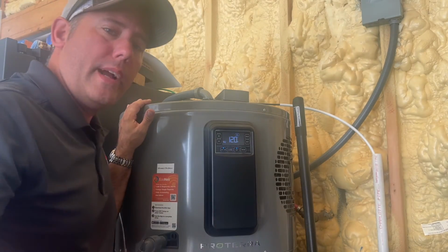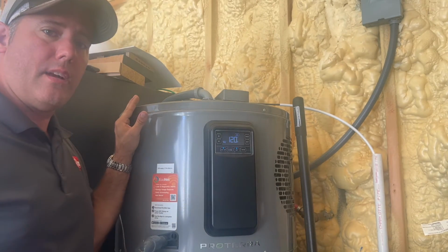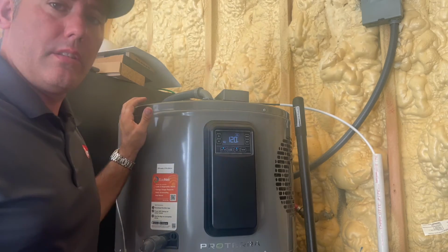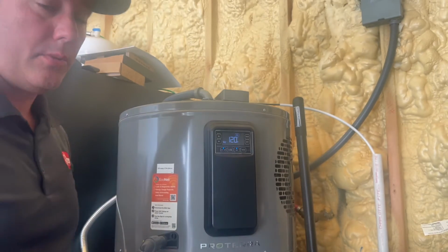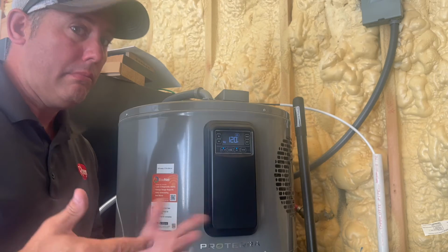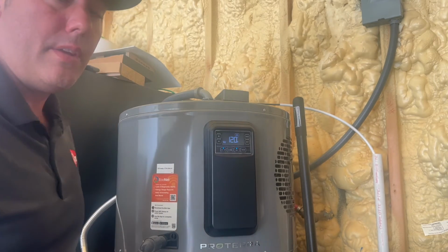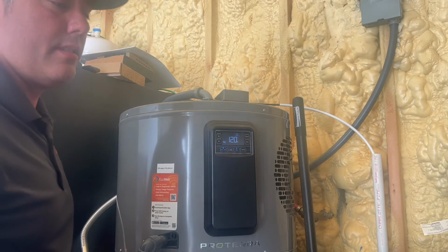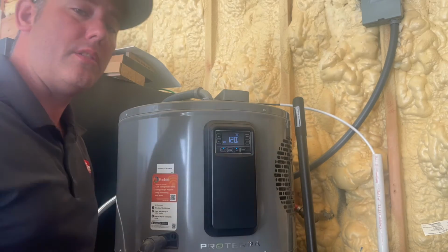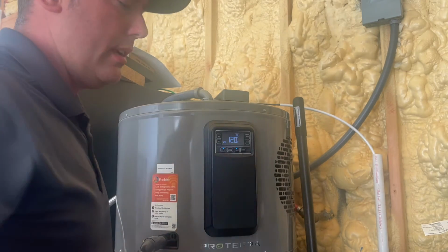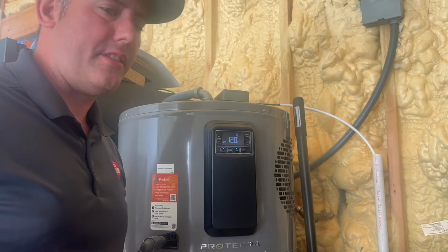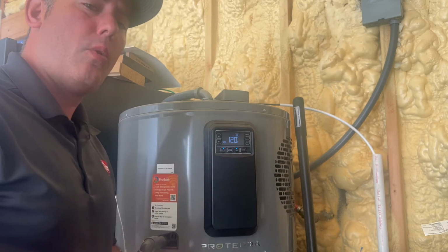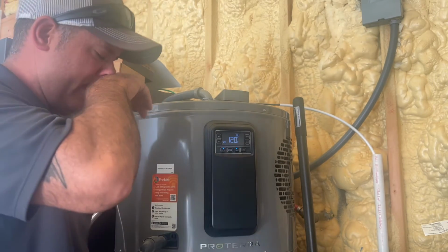Now, if you do turn your water back on and you hear that noise and you suspect water's running out somewhere, well, easiest place to look, TPR. Do we have a pressure or a temperature problem? Has it worn this TPR valve out? Is it older than 3 years? Let's go to the outside of the house, wherever that runs out. We can look and see if there's water running there. Going around to all of the faucets also, easy check. Let's go see if we've got any water dripping on any faucets. Okay.